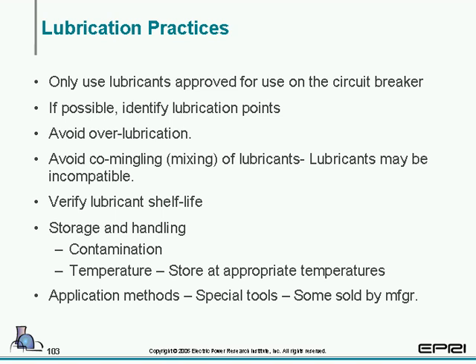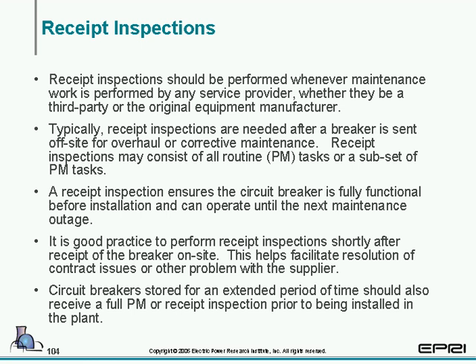Verify lubricant shelf life. For storage and handling, you have to avoid contamination and store it at the proper temperature and so forth. There are also application methods and special tools. Some of these special tools for lubricating a breaker, either during a PM or overhaul, are even sold by the manufacturer themselves, because the manufacturer developed them for maintaining the breakers in their own shops. Receipt inspections: this is something that we've learned in the nuclear industry, and I'm going to emphasize this point.